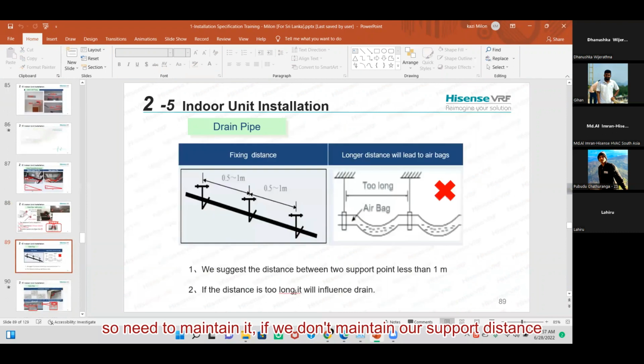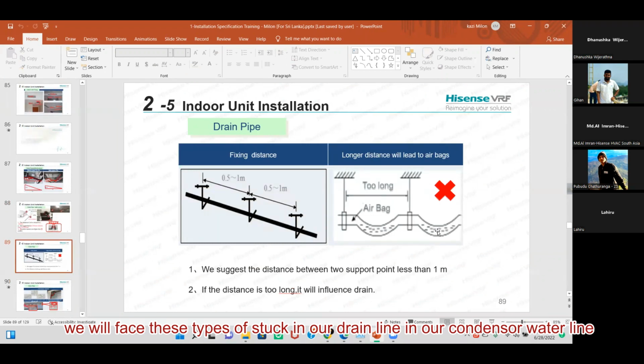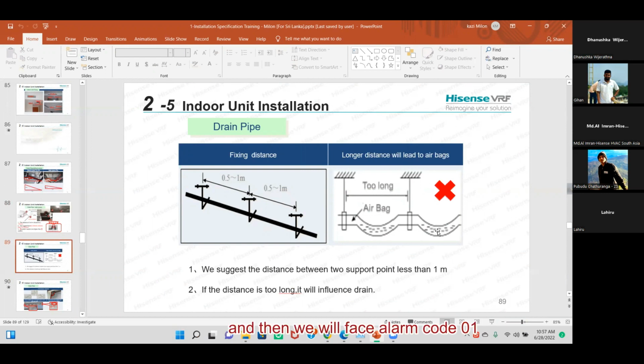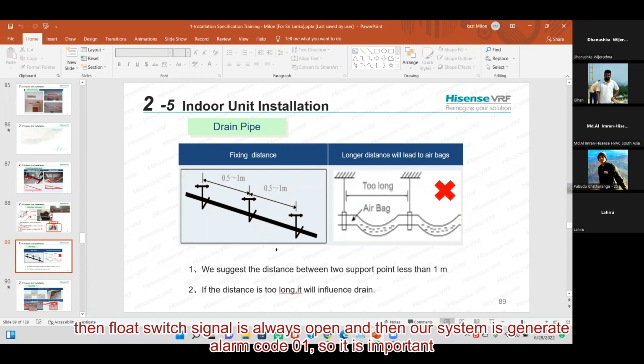If we don't maintain the support distance, we will face sag in our drain line, our condensate water line. Then we will face alarm code 01. When water cannot go easily and the pump cannot pump the water, the float switch signal is always open. Then our system generates alarm code 01. So it is important.